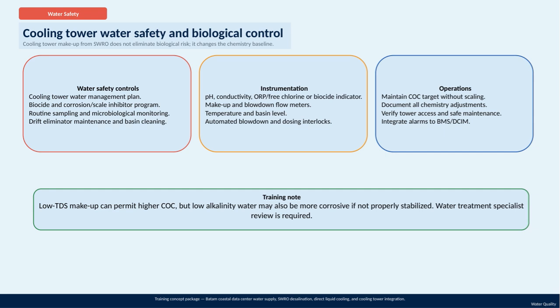Instrumentation plays a vital role in monitoring parameters like pH, conductivity, oxidation reduction potential, or ORP, and free chlorine or other biocide indicators. We also monitor makeup and blowdown flow meters, temperature, and basin levels, using automated systems for blowdown and dosing interlocks to maintain optimal conditions. On the operations side, it's crucial to maintain the target cycles of concentration, or COC, without allowing scaling to occur. All chemical adjustments should be carefully documented. Ensuring safe access to the tower for maintenance is a must, and integrating alarms into the building management system or data center infrastructure management helps quickly identify any issues. Finally, a key training note.